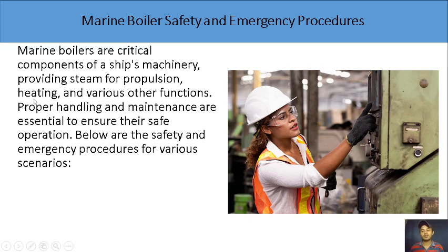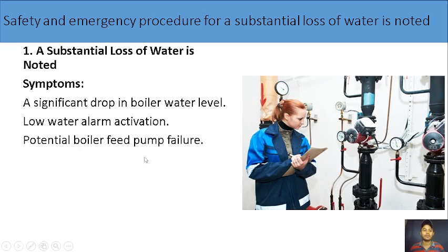Okay, so marine boilers are critical components of a ship's machinery, providing steam for propulsion, heating, and various other functions. So proper handling and maintenance are essential to ensure their safe operation. Below are the safety and emergency procedures for various scenarios. Okay, first, for a substantial loss of water. The symptoms: a significant drop in boiler water, which you can see in the sight glass, then the low water alarm is activated, so there will be an alarm, and potential boiler feed pump failure. These are the symptoms that there will be a substantial loss of water in your boiler.